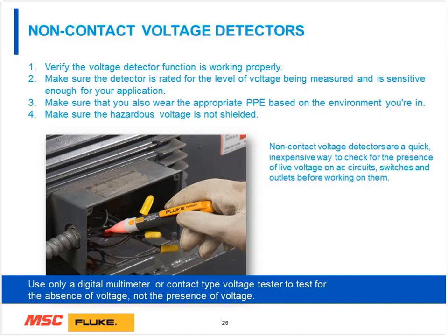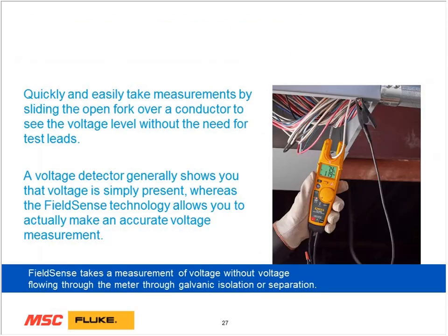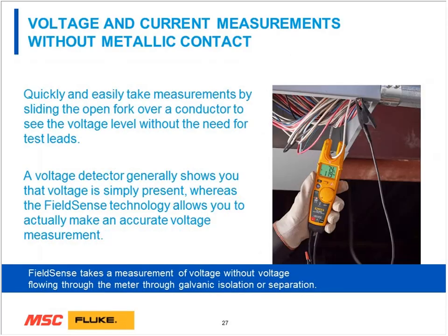Use only the digital multimeter or contact type voltage tester to test for the absence of voltage, not the presence of voltage. A lot of these we use if we're looking at a circuit to just see if it's hot or not. But if there's something wrong with it or you're not getting a very clear indication of active voltage, I still wouldn't trust myself to touch that contact. There's voltage and current measurements without metallic contact.